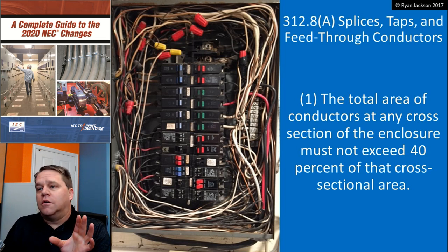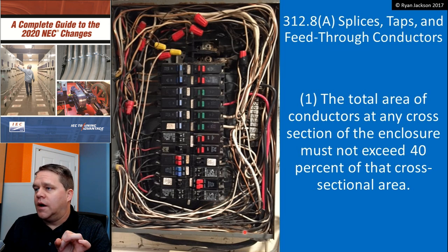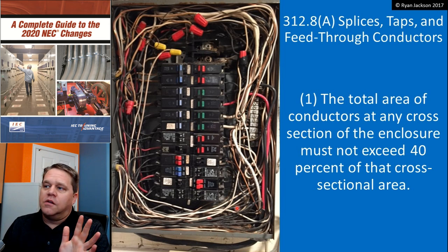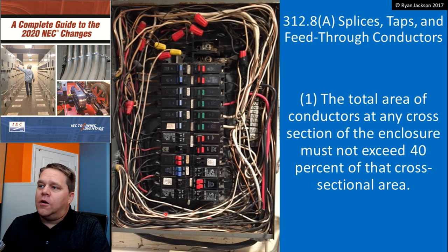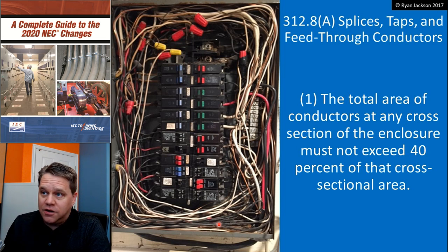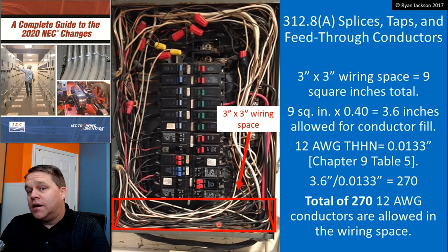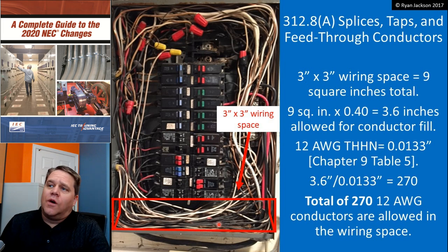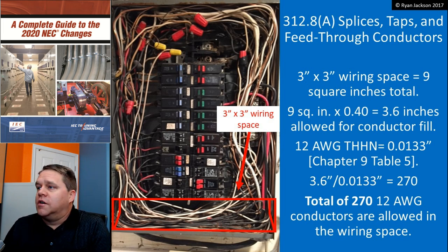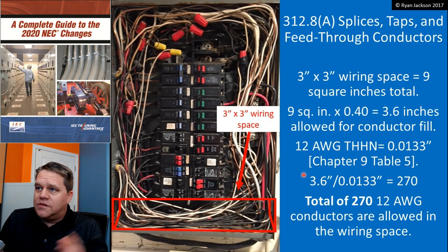I don't think it's possible because I've done the math and it's very surprising. Let's say the wiring space is three inches by three inches, and let's pretend all of these are 12-gauge wire — how many 12-gauge wires could you put in that area before violating this section? The answer is 270. You're not going to violate this section even if you wake up and say you're going to. Splice as much as you want in a cabinet that contains a panelboard — you're not going to violate this rule.